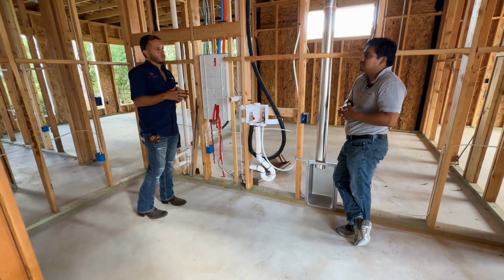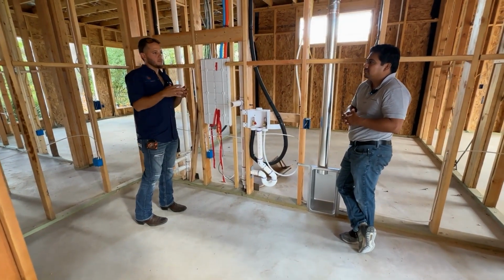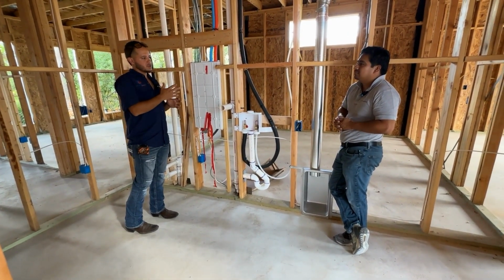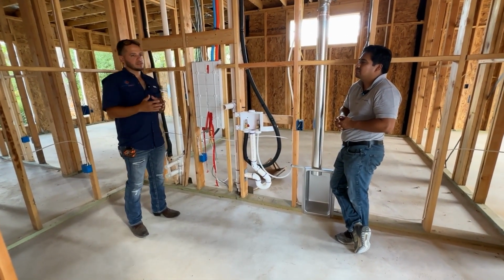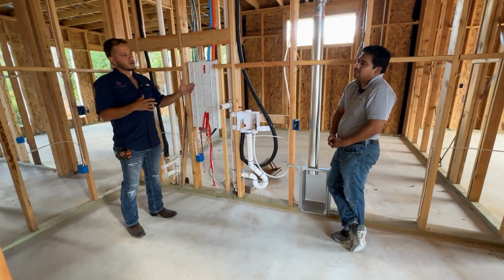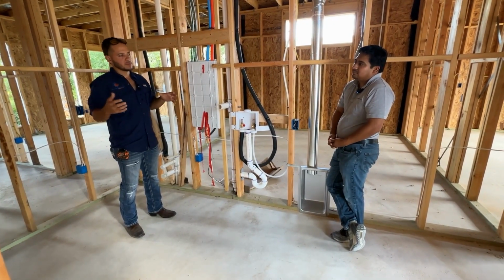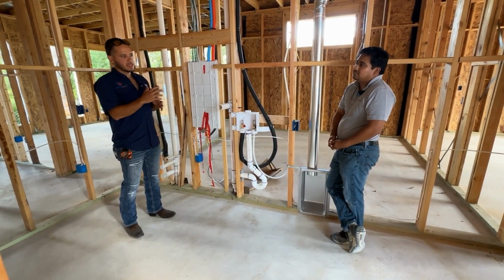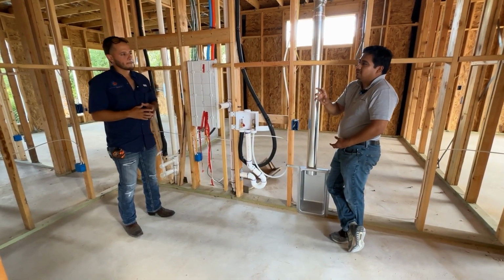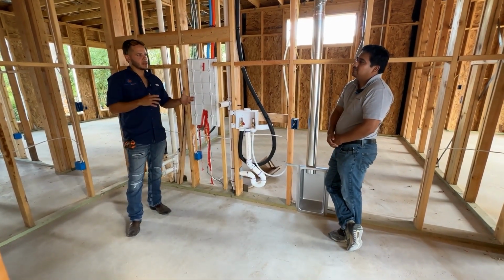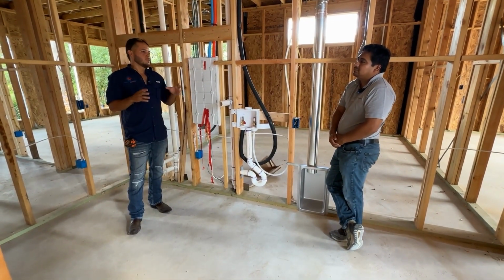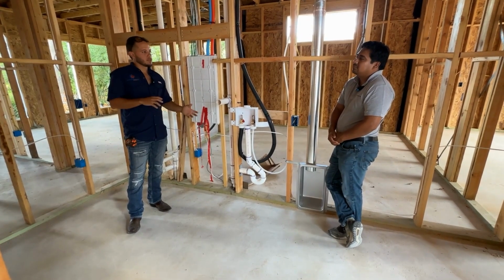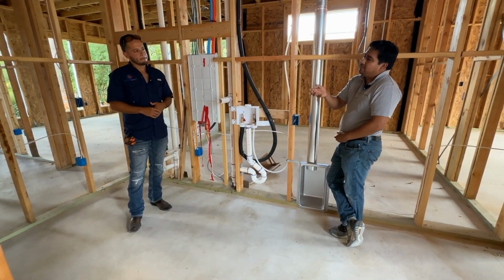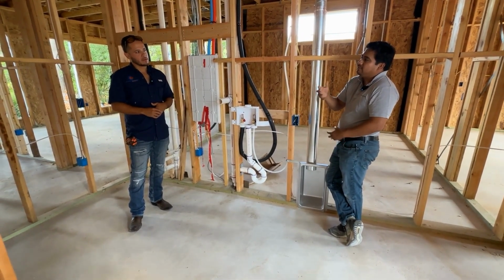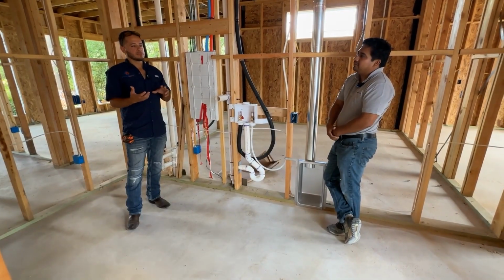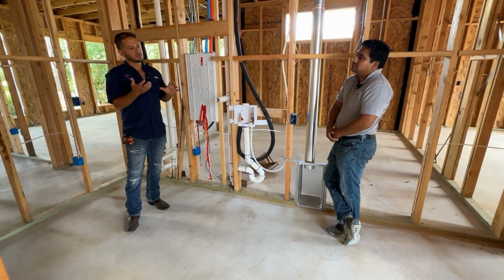The other thing is we're allowed to do that because we use dampers in each duct as well. So even with a bigger duct, that doesn't mean you're going to have more CFMs, because it's controlled by that damper too. We size it to a certain CFM, and whenever the system is on, the damper regulates it to what the room needs. Could you raise it later since you have bigger capacity? Since it's a bigger duct, we actually reduce it.